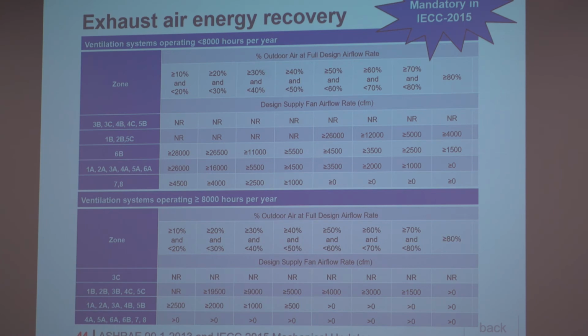Having said that, I know we only ship about 30% of our units with that. So there's a lot of people that are finding loopholes, unfortunately. And so what we try to do is limit the numbers of loopholes. As you look at the developments that are happening in the standards, it's usually an attempt to either go more stringent or reduce loopholes. Because that is a really good thing for the middle of the country, because in 4 and 5 and 3, you have heating and cooling savings. And it's of course really important in the really cold climates too because of the dominance of the heating. It still pays off in the hot climates too because of the downsizing of the cooling equipment that you can achieve by doing energy recovery ventilation. So that's why climate zone 1A and 2A actually have some requirements too. This was a cost justified table. So you can probably argue until you're blue in the face, but this is the table. And it's the same regardless of which version of the standard you're in, 90.1 or IECC.